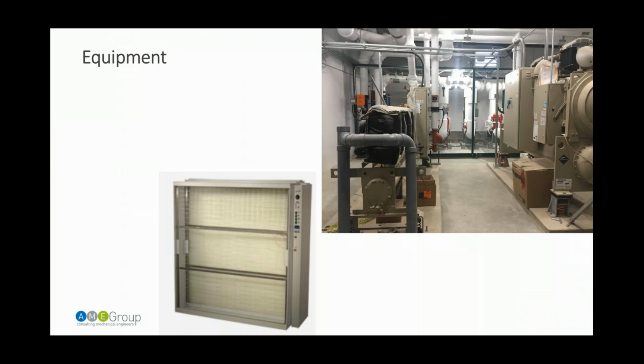And so moving from that, just simple equipment efficiencies that we looked at. We've got magnetic bearing chillers, so increasing the efficiencies on our low cooling side of things. The mag bearing chillers really operate more efficiently at lower loading compared to typical chillers. And just to make sure that we were okay on our really low loading before the building's really fully occupied, and in the shoulder seasons, we've got one smaller 60-ton scroll chiller that's going to deal with those really small loads in the building.